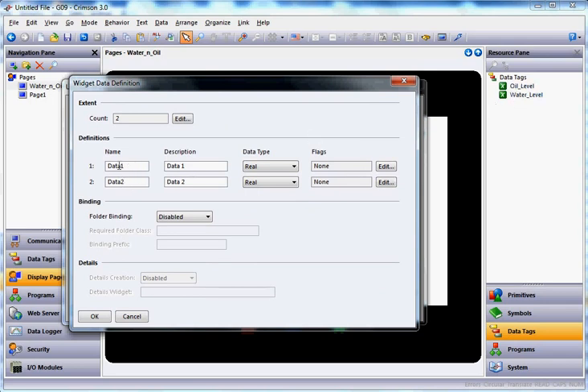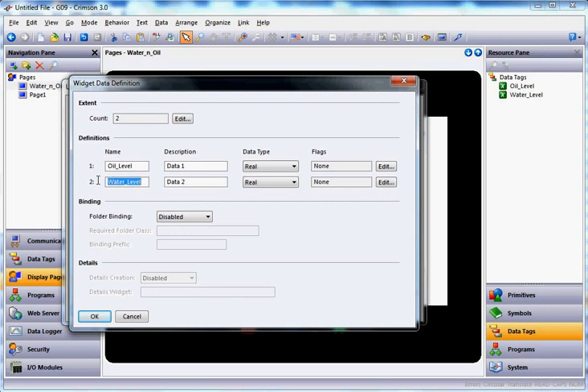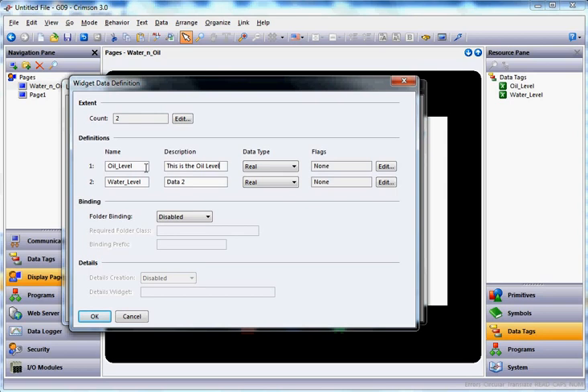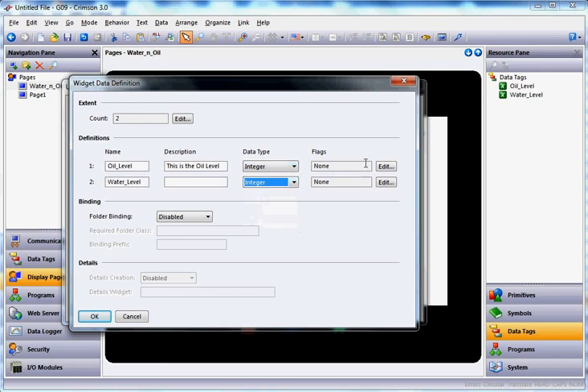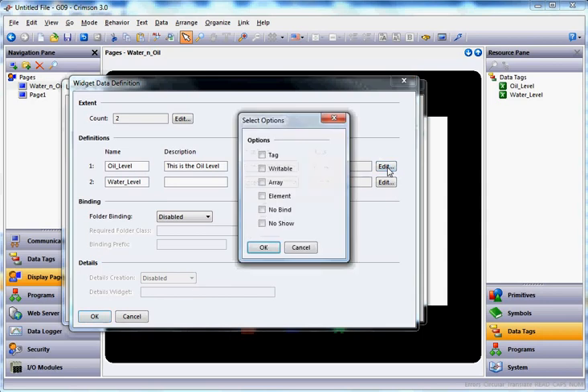Now you notice that you're in the section where you're going to be defining the widget. What you want to do here folks is you want to make sure that the name category here is spelled the same way as it is over here. So I'm going to click on this data here, I'll delete that and I'll type oil underscore level. Capitalization doesn't matter, but it does have to be spelled the same way. This one here, I'll delete it as well and I'll type water underscore level, enter. Don't forget any time you type in our software, hit the enter key. And if you want to change the description you can. Now both of these right now happen to be integer types, you can see the X here, so I'll hit the pull down here and I'll choose integer, integer. And since we are only reading these values into this widget, when we hit the edit button here to define the flag type action, these are going to be just a tag. We're not writing anything, we're just reading them in.